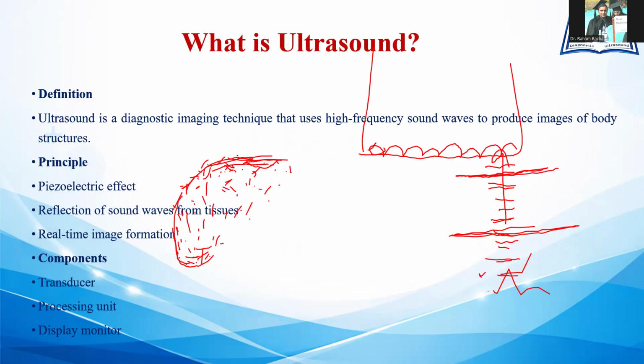So, according to the echo return time, their location is placed, and based on their echo amplitude, if the reflector is strong enough, for example, this is a reflector, and just assume that it is a strong reflector, so the echo reflected from it will have high amplitude, and they will mark a very bright dot over here. And if there is any weak reflector, the echo will be reflected with low amplitude, and that will mark a dark dot on the ultrasound image. In this way, the ultrasound image will form from black to white and different gray shades. That's why the image is also called a grayscale image.